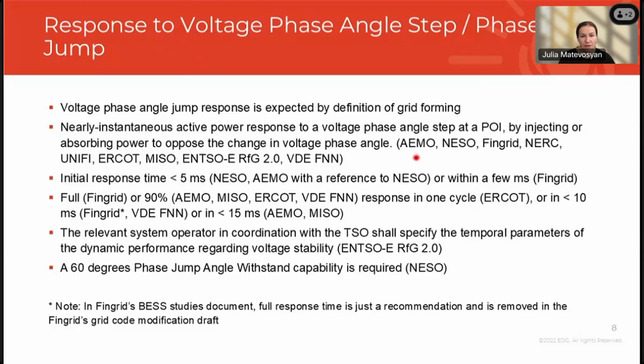So as you can see, most of the requirements that we have reviewed ask for nearly instantaneous active power response to voltage phase angle step at the point of interconnection. And that basically looks at injecting or absorbing active power to oppose the change in voltage phase angle. Initial response time is defined by National Grid ESO as 5 milliseconds, and then AEMO also specifies it the same way, but they refer to the ESO requirement.